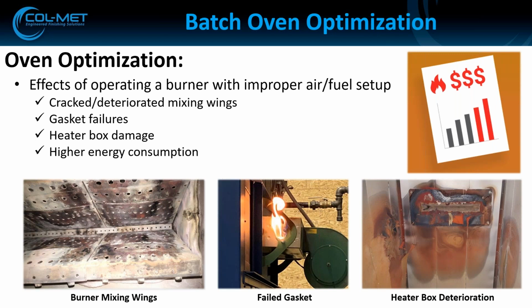But if the combustion blower wheel gets dirty, or if powder gets pulled in and starts clogging up the mixing wings, what you have is not enough air pressure across the burner, but you still have the same amount of fuel that you had coming in. So it kind of causes the burner to go fuel rich. And that eventually leads to cracked mixing wings and gasket failures and heater box deterioration and higher fuel bills, because basically if the burner's not running optimally, you're going to be using more fuel to get the same BTUs.